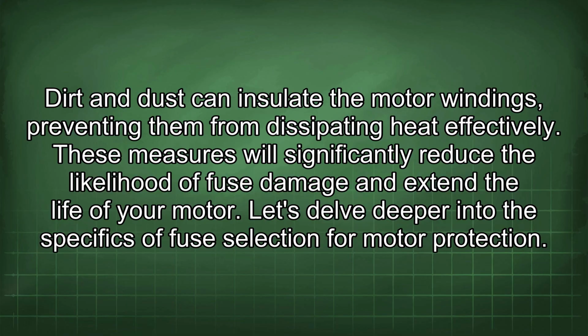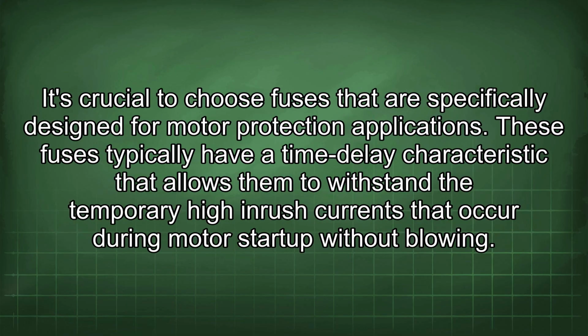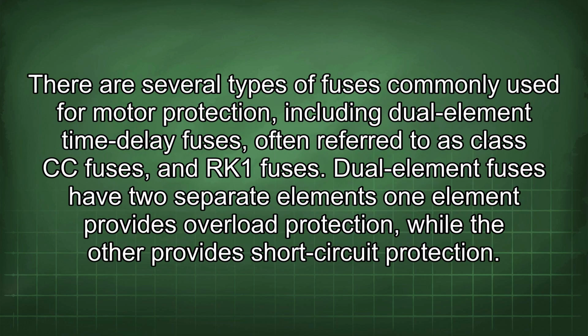Let's delve deeper into the specifics of fuse selection for motor protection. It's crucial to choose fuses that are specifically designed for motor protection applications. These fuses typically have a time delay characteristic that allows them to withstand the temporary high inrush currents that occur during motor startup without blowing. There are several types of fuses commonly used for motor protection, including dual-element time delay fuses, often referred to as Class CC fuses, and RK1 fuses.